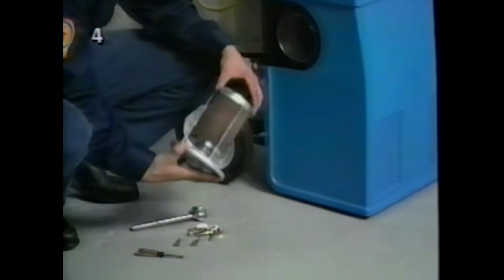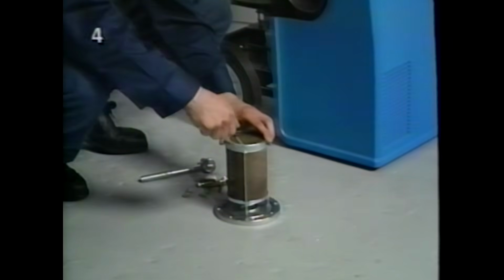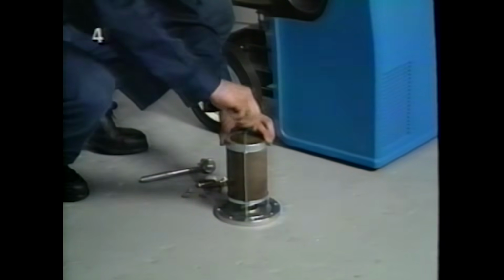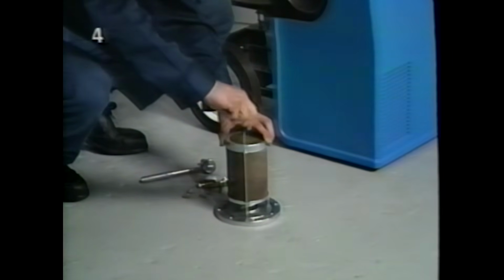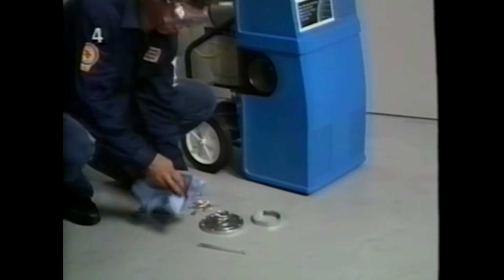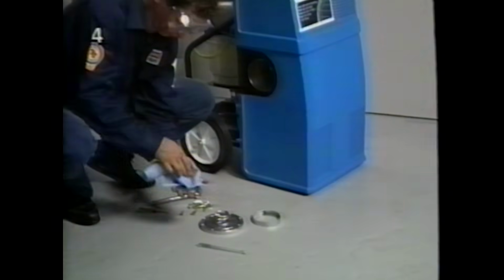Undo the bolts that hold the filter dryer cap to the shell. Then take out the tie rods and remove the core from the brackets. Clean off all the internal parts inside the filter dryer assembly. Filter dryer reassembly is exactly the same as installing the core during setup. The complete procedure is contained in Section 1B of the service manuals.